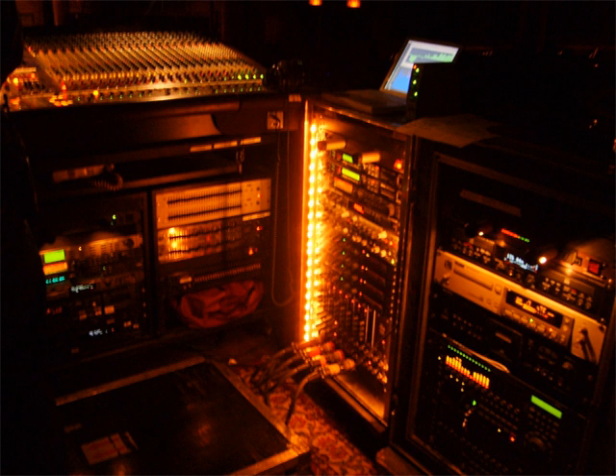Typically, a piece of equipment being installed has a front panel height 1/32 inch (0.03125 inches or 0.794 millimeters) less than the allotted number of U. Thus, a 1U rack mount computer is not 1.752 inches (44.5 millimeters) tall but is 1.721 inches (43.7 millimeters) tall. 2U would be 3.473 inches (88.2 millimeters) instead of 3.504 inches (89.0 millimeters). This gap allows a bit of room above and below an installed piece of equipment so it may be removed without binding on the adjacent equipment.